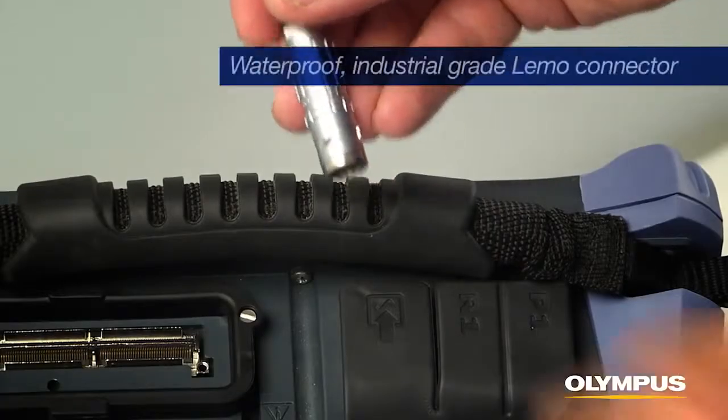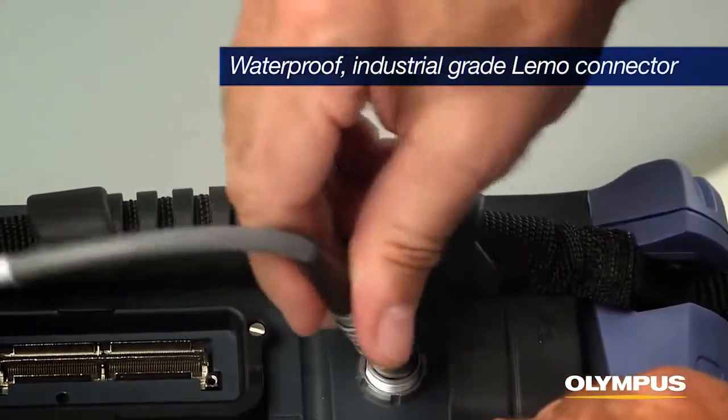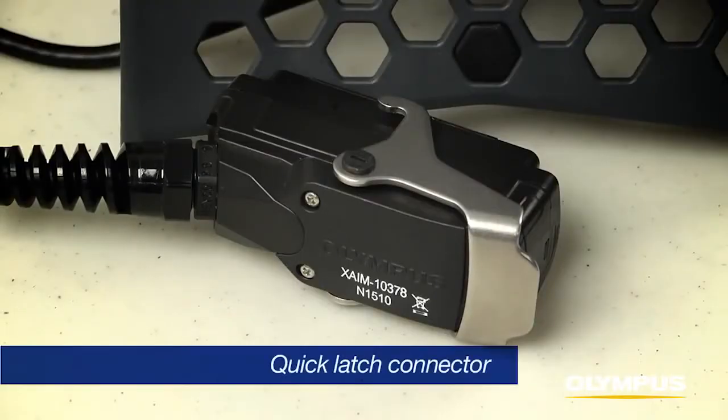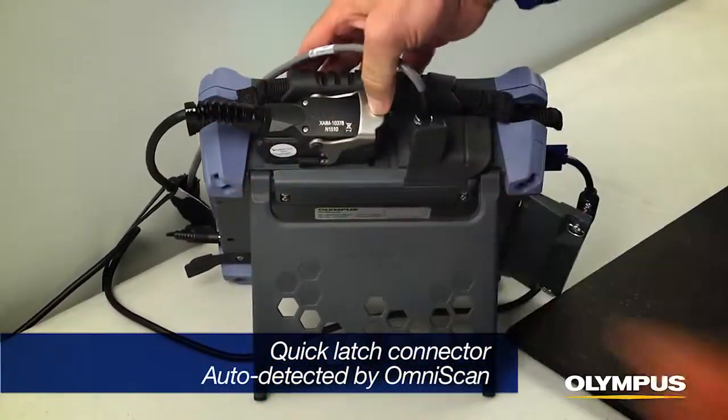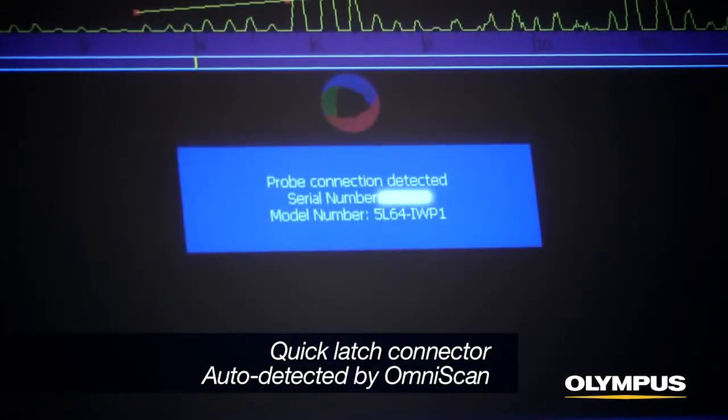The RollerForm encoder is connected to the instrument with a waterproof industrial grade Lemo connector. The RollerForm phased array probe is connected to the instrument with a quick latch connector. It is auto-detected by the OmniScan SX or MX2 and will update the phased array configuration for the installed probe.